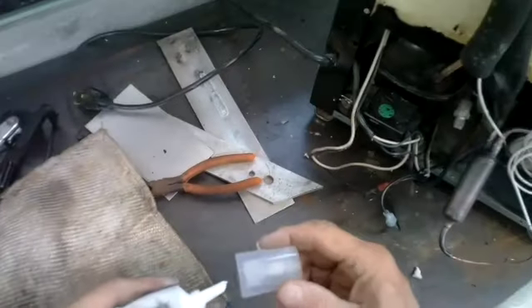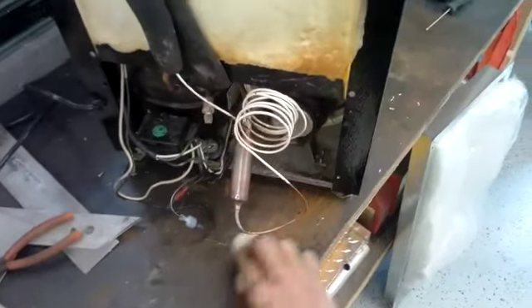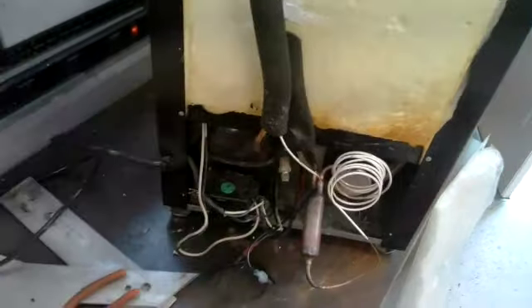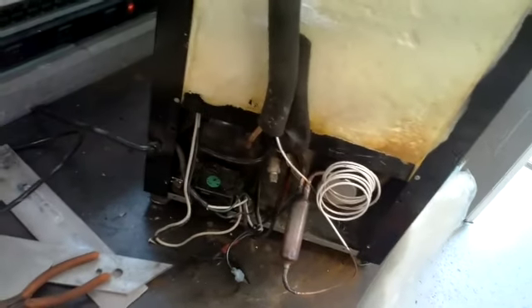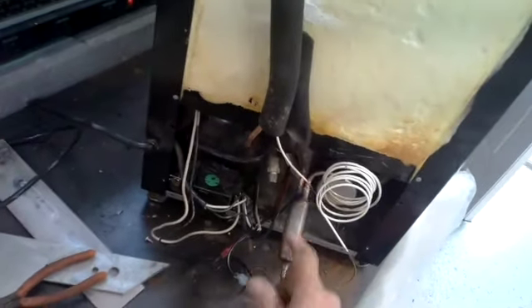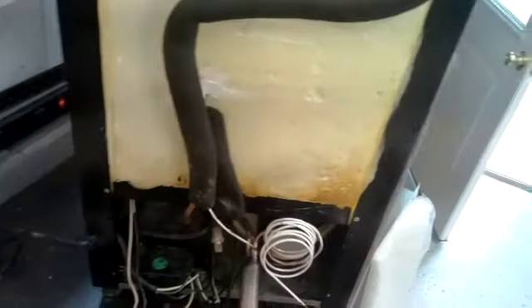The back cover also has some insulation to help keep the heat out or keep the cold in. All right, so that's that. The next thing we're going to do is check it for leaks, check my soldering joints here. And if all else is well, we'll pull a vacuum on it or do a sweep charge, and then mount this filter, clean it up. All right, so stand by.